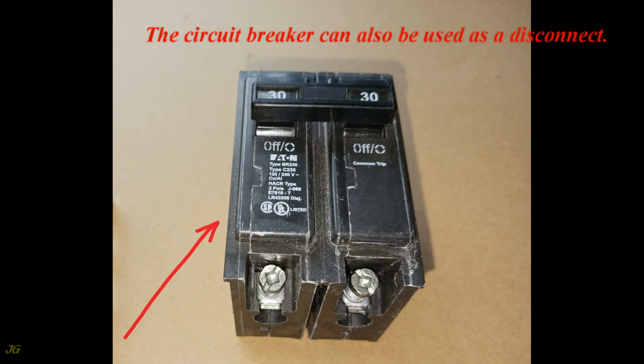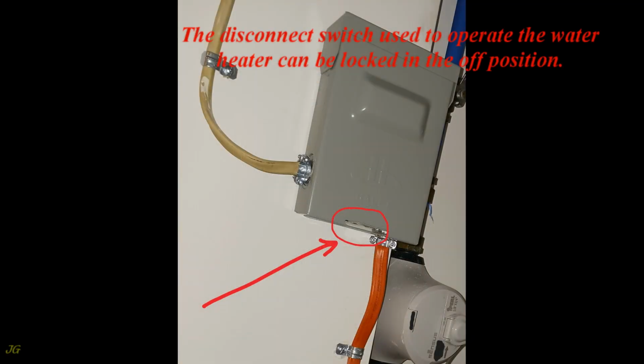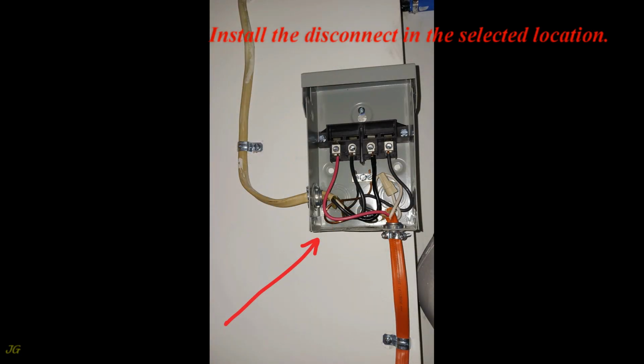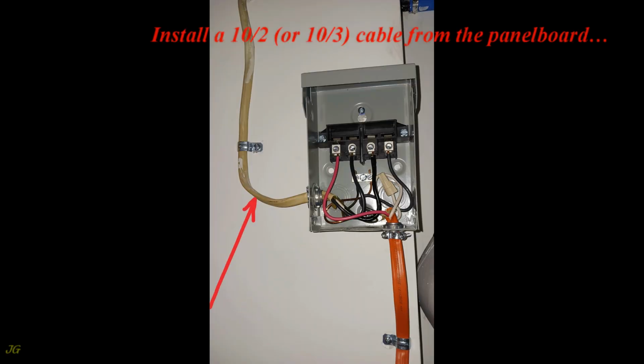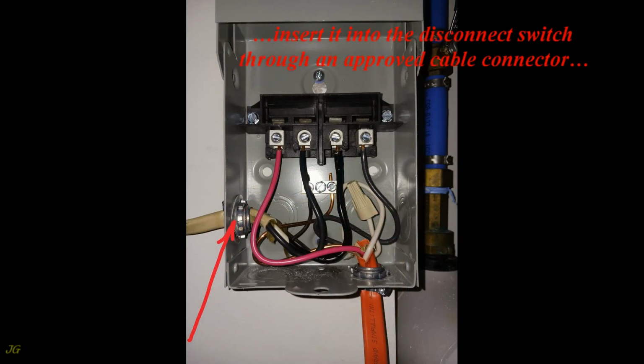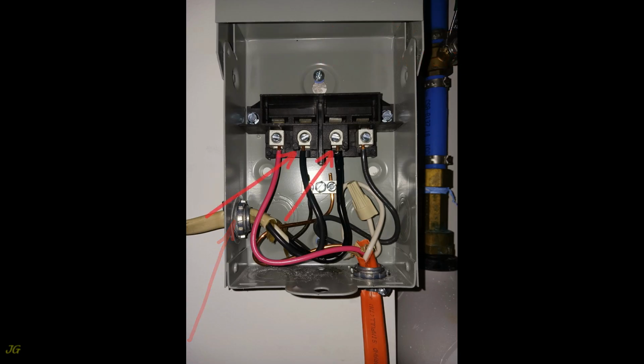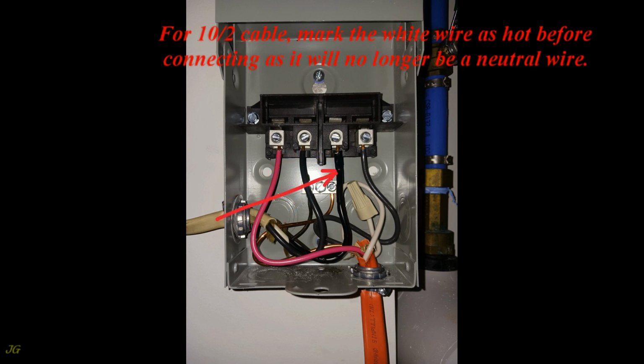The circuit breaker can also be used as a disconnect. The disconnect switch used to operate the water heater can be locked in the off position. Install the disconnect in the selected location. Install a 10-2 or 10-3 cable from the panel board. Insert it into the disconnect switch through an approved cable connector, and connect it to the disconnect line terminals. For 10-2 cable, mark the white wire as hot before connecting, as it will no longer be a neutral wire.